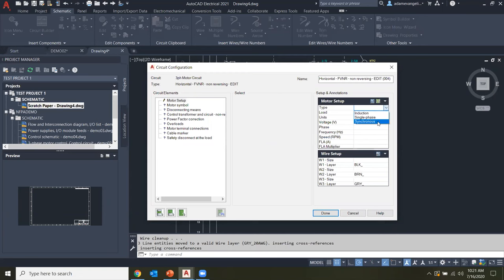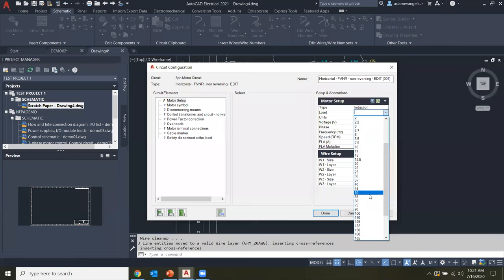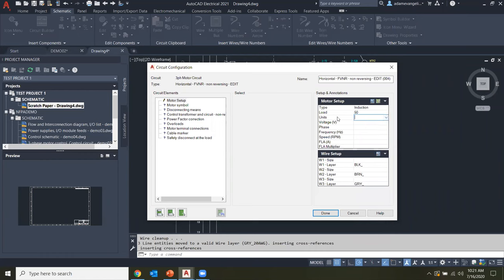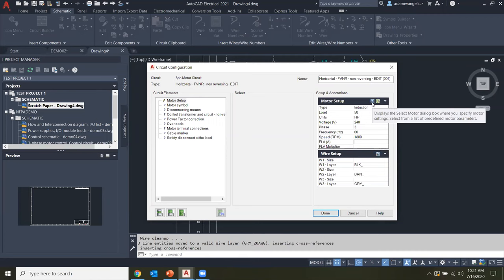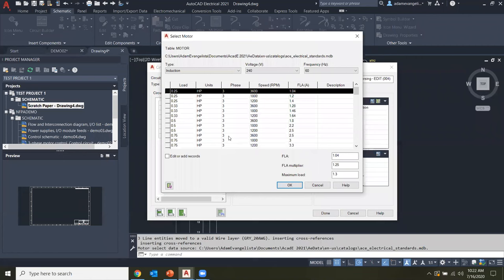We can choose up to 50 horsepower, voltage — we'll do standard 240 — number of phases, frequency, speed in RPM, and FLA (full load amperage). You can manually fill those out or click the magnifying glass to select the motor in more granular terms from a Microsoft database standard. If you're wondering where this information comes from specifically, it's coming from your database. This dialog box also includes an Edit button if you want to write directly to it, given the right permissions.